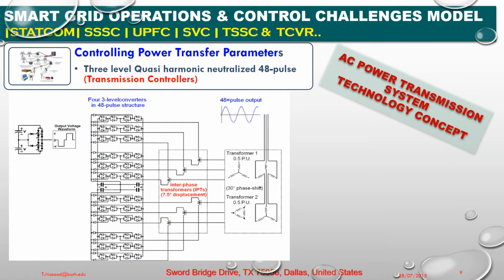For a high power FACTS controller, from the point of view of the AC system, even a 24-pulse converter without an AC filter could have voltage harmonics higher than the acceptable level. In this case, a single high pass filter tuned to the 23rd to 25th harmonic, located on the system side of the converter transformer, should be adequate. An alternative is to go to 48 pulse operation with eight 6-pulse groups with one set of transformer, the 48 pulse converter. The phase shift is an interphase transformer with 7.5 degree displacement.